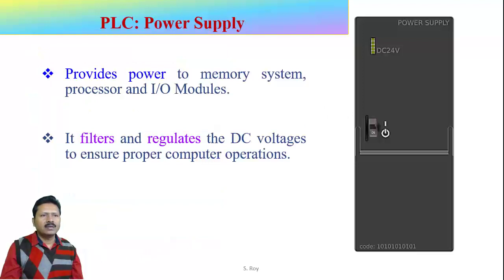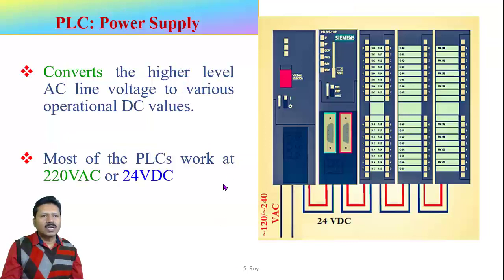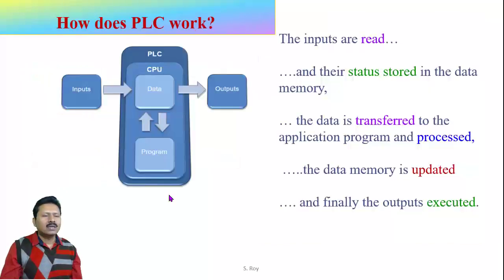The power supply provides power to the CPU and all electronic accessories, including all input/output modules and interface modules. Input/output modules and processors operate on DC voltage, normally 24V DC. The power supply module must have the facility of filtration and regulates the DC voltage to ensure proper power supply to the CPU and other accessories. It converts the high level AC supply voltage — normally 120 or 240V AC — to the required 24V DC operational voltage.